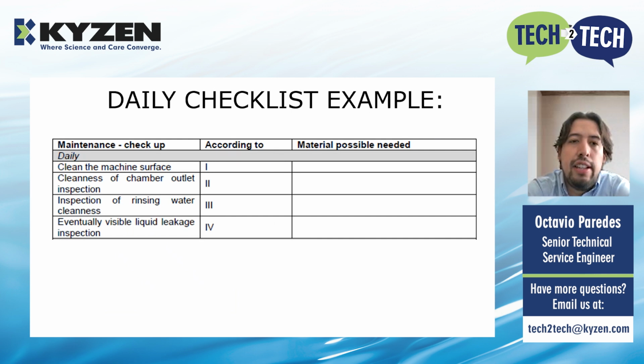This is the daily checklist example: clean the machine surface, clean the chamber outlet, inspect the rinsing water cleanliness, and inspect for any visible liquid leakage. As mentioned before, all these activities can be done in a couple of minutes, but they're important for the process.